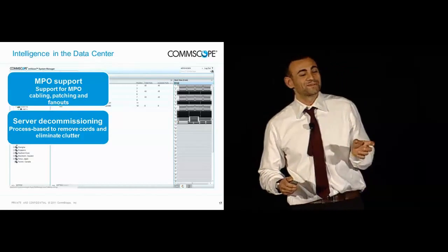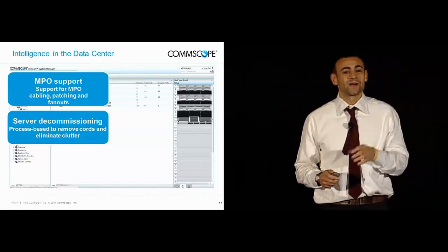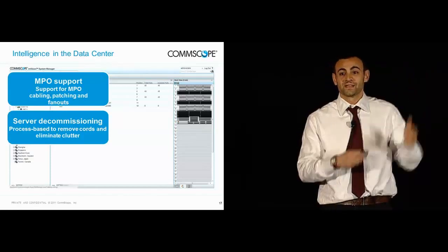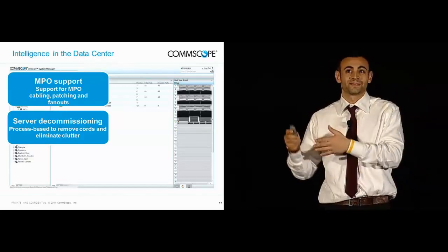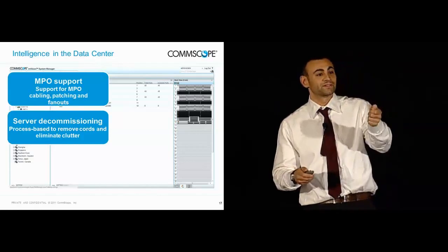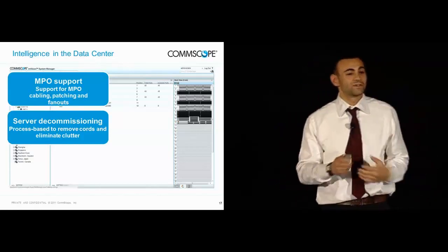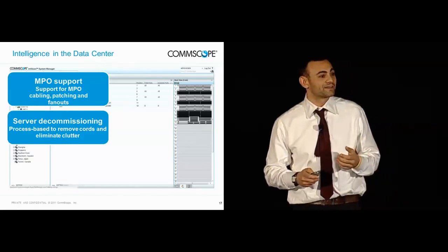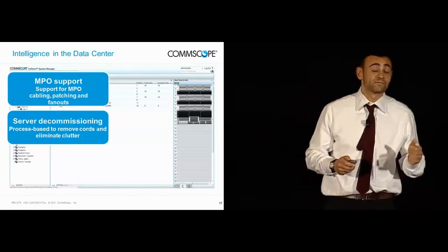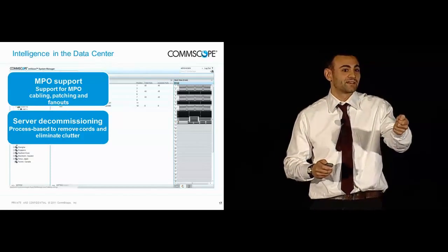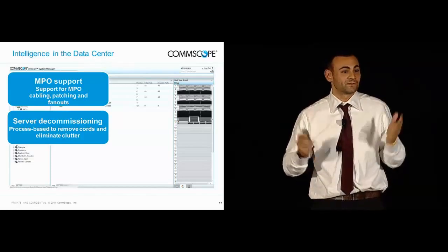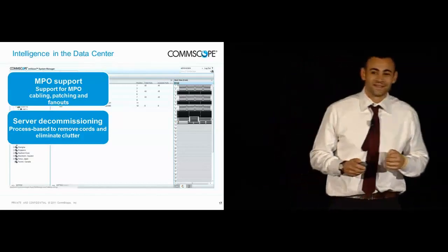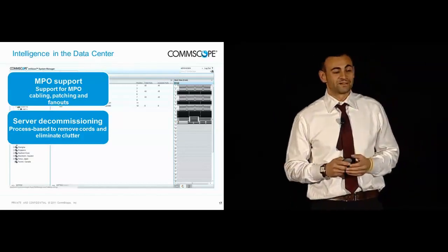Because typically when you don't decommission a server properly, you have cabling left in place, falsifying what you think is an open port because it's plugged into a switch, and you really don't know if that patch cord is active or not. And the reason is, well, of course you know, right? It has light. Well, if a PC or a server is turned off, you're not going to see light out of that port, right? So it may give you a false positive.